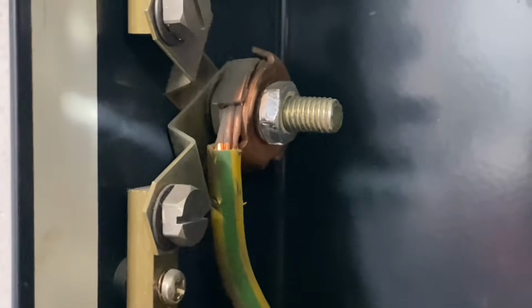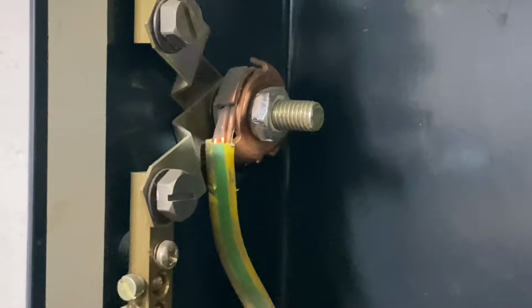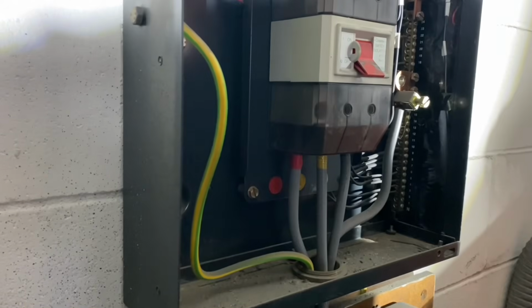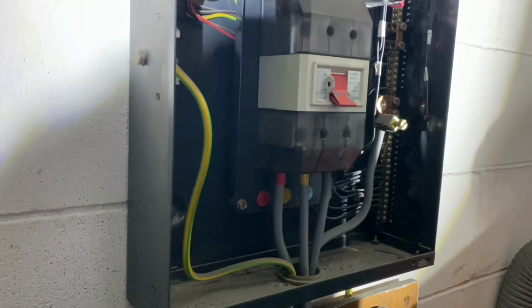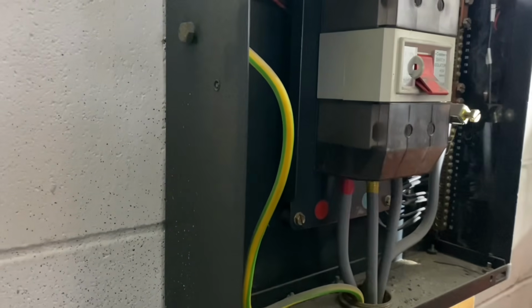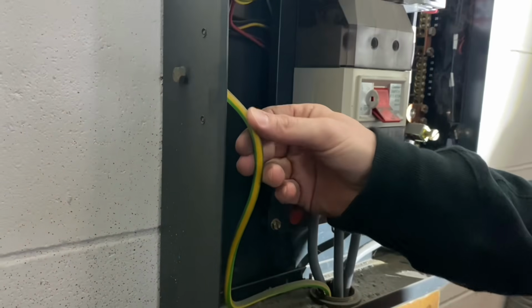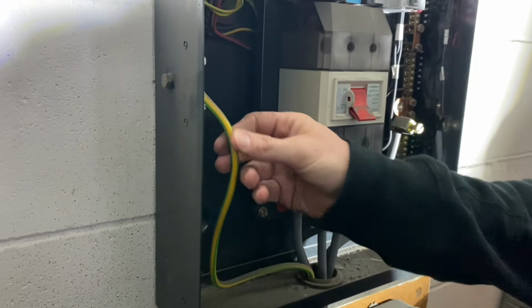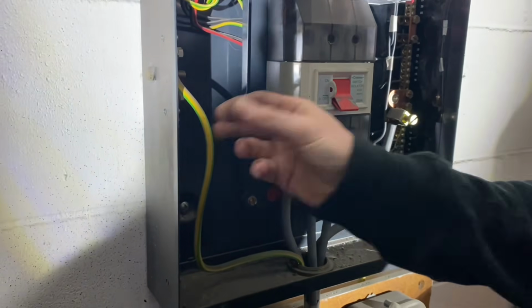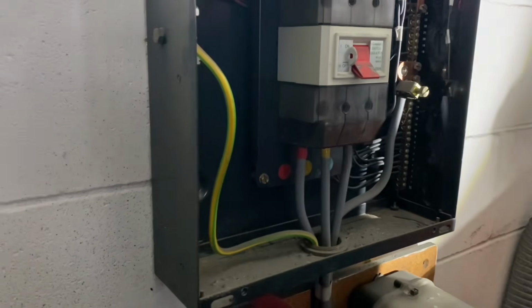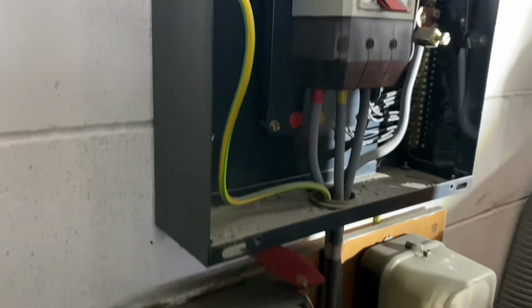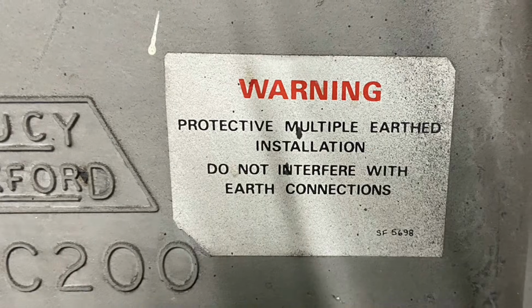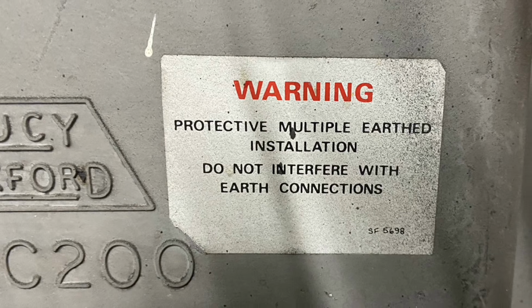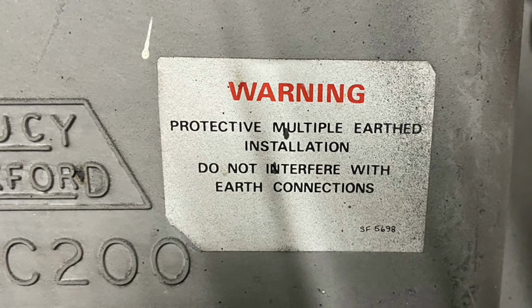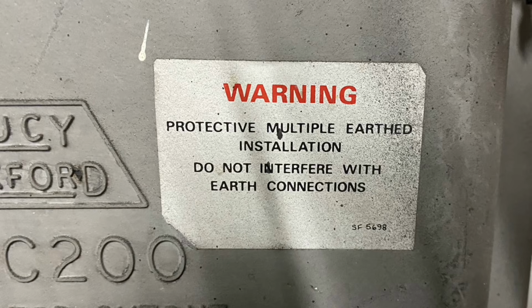If we were not to disconnect it, then we'd have a problem with parallel earth paths via the extraneous conductive parts, through the bonding and so on. We want to know the external earth fault loop impedance, and by removing this earth, that is just the external, nothing internal. And we've got an earthing arrangement of TN-C-S. So what's the maximum reading for the external? On a PME or TN-C-S, it's 0.35 ohms.